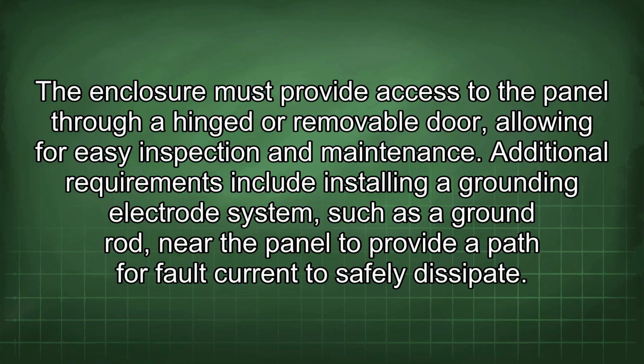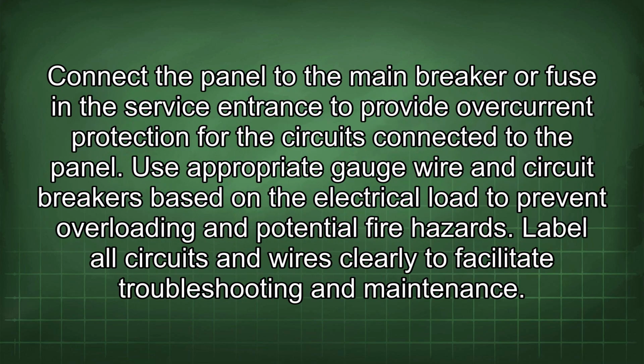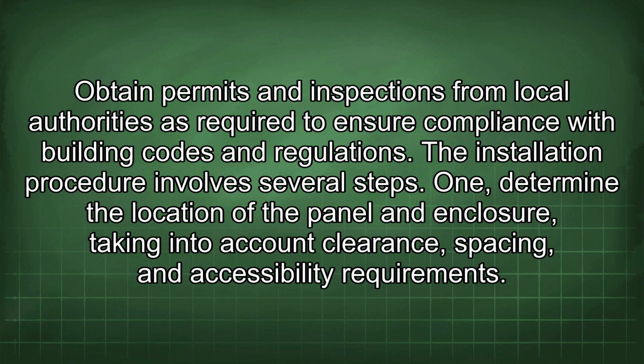Additional requirements include installing a grounding electrode system, such as a ground rod, near the panel to provide a path for fault current to safely dissipate. Connect the panel to the main breaker or fuse in the service entrance to provide overcurrent protection for the circuits connected to the panel. Use appropriate gauge wire and circuit breakers based on the electrical load to prevent overloading and potential fire hazards. Label all circuits and wires clearly to facilitate troubleshooting and maintenance. Obtain permits and inspections from local authorities as required to ensure compliance with building codes and regulations.